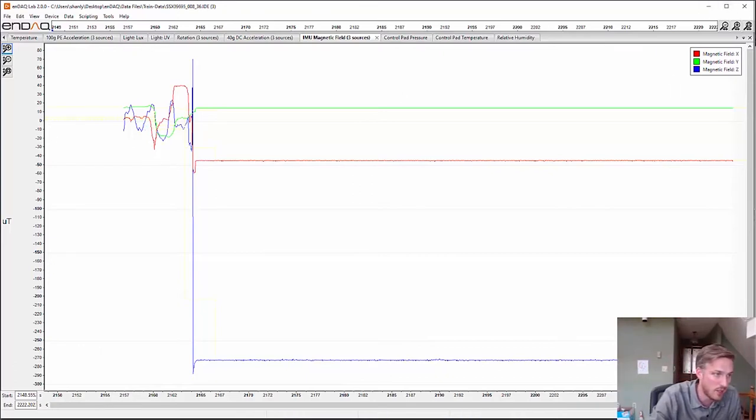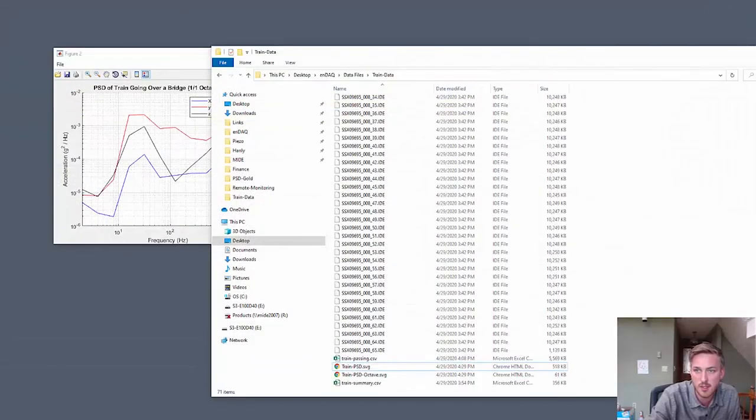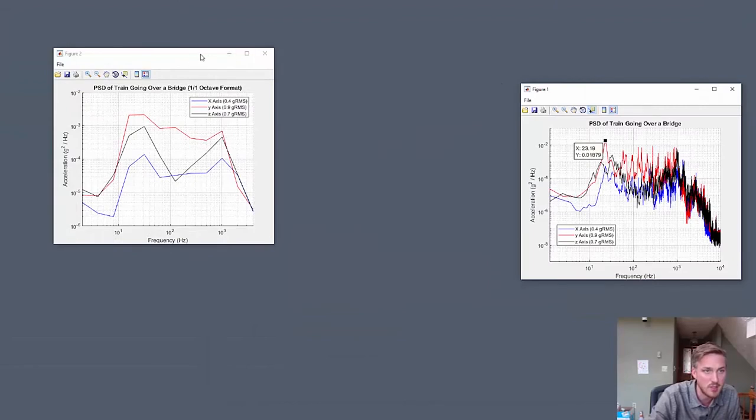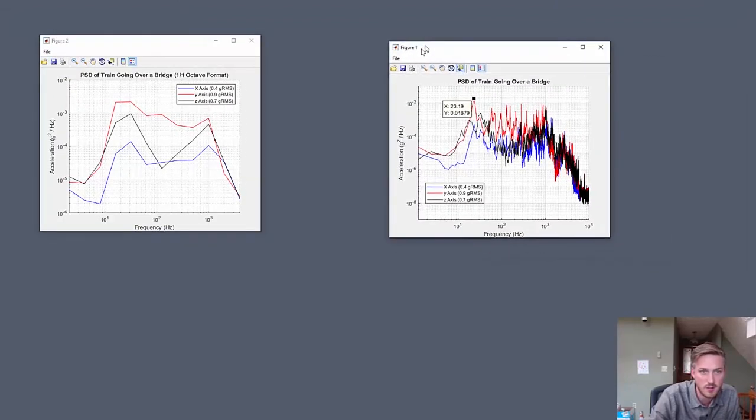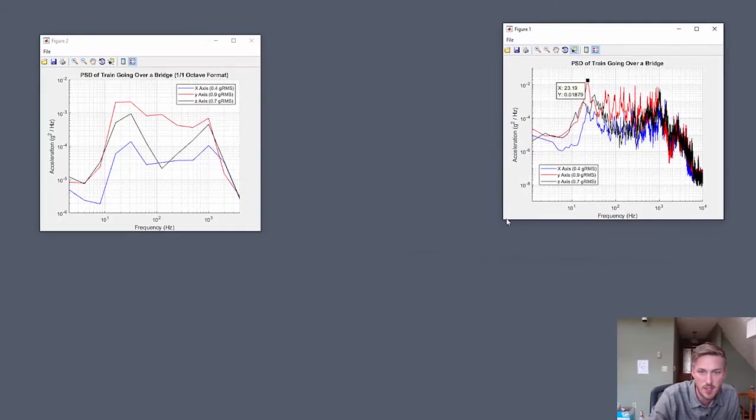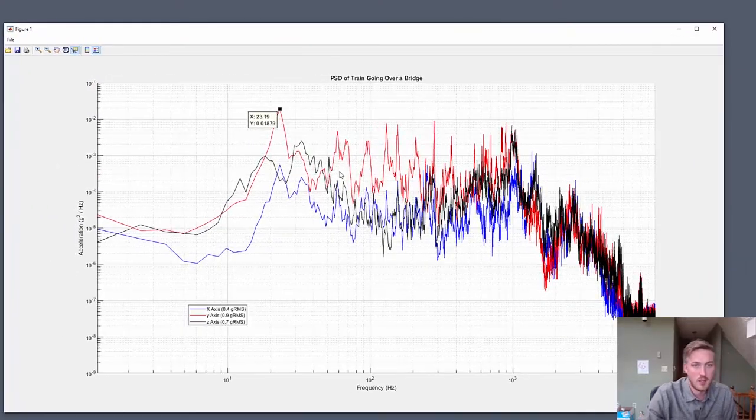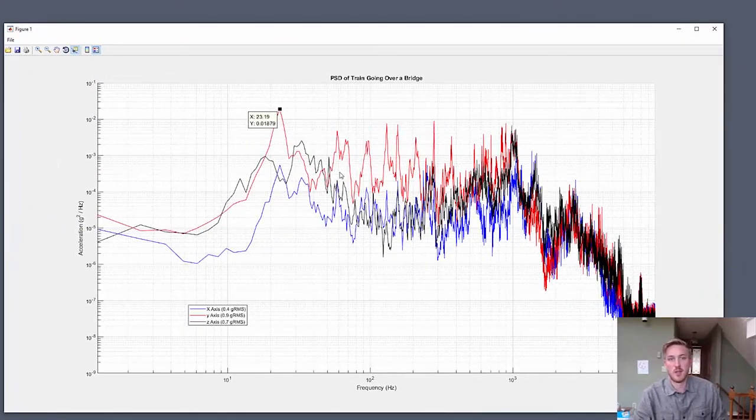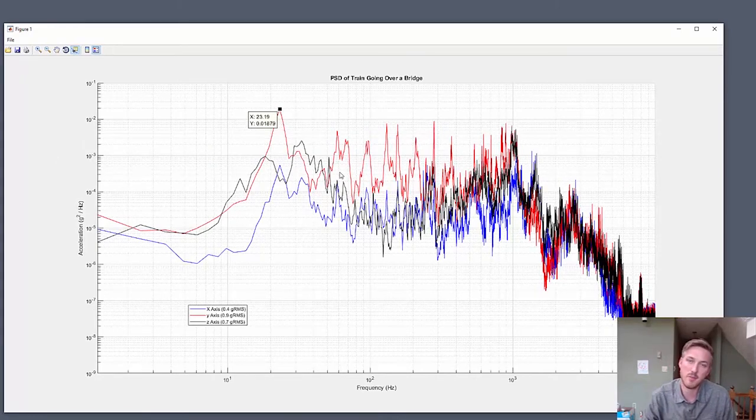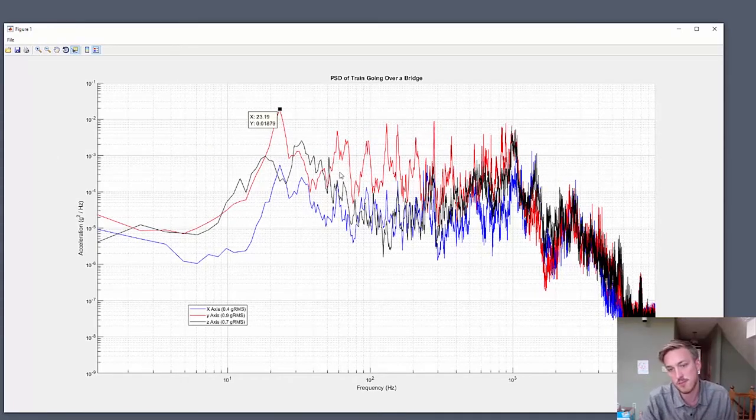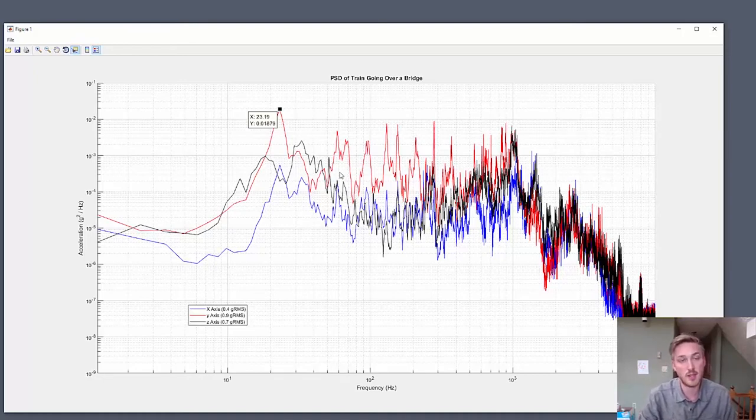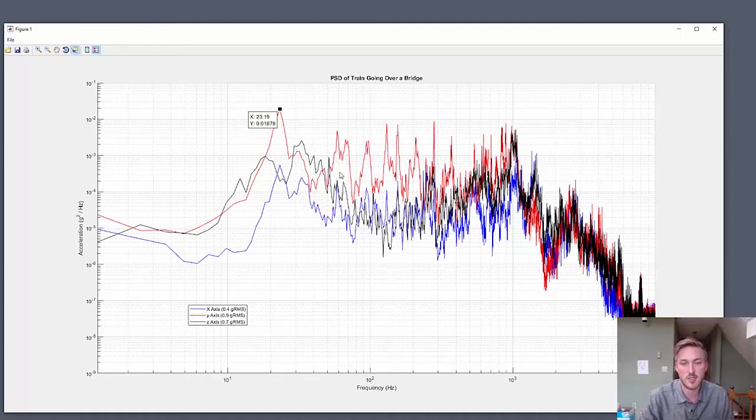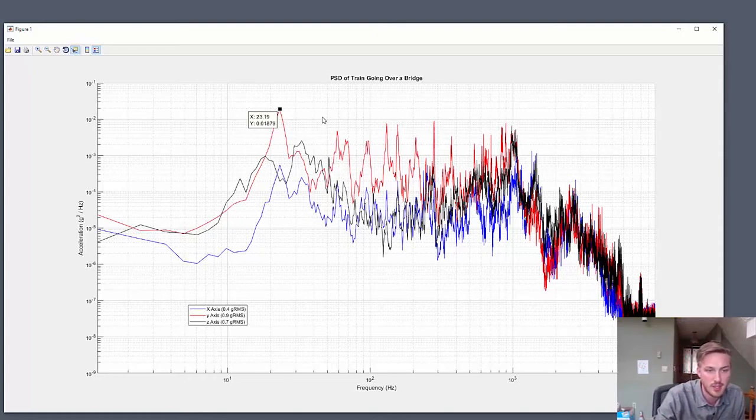So let's go into the PSD data from the toolbox. So here it is in the vibration data toolbox. I exported that acceleration time series data in the X, Y, and Z, and then calculated power spectral density using, I think, a one Hertz frequency bin width.